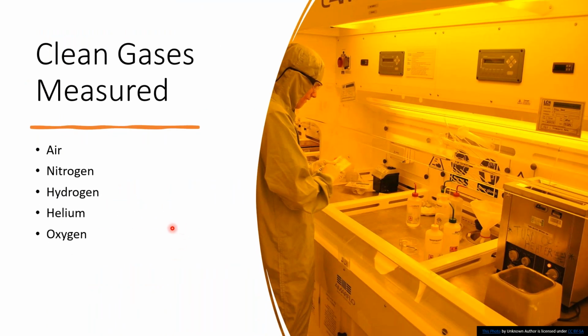Other gases that we measure on a regular basis, like I mentioned, we do a lot of airflow measurement. We do a lot of hydrogen, nitrogen, helium, oxygen, you name it. We're doing these on a regular basis. And some people say, well, you're measuring air, everybody can measure air. And it's like, yes, but we're measuring air in lots of different environments, whether it be food and beverage, where they're maybe using heated air and need a clean instrument to do that, or a pharmaceutical, or maybe you want to find out what department is using your compressed air. So these are all different applications and why thermal mass could be effective and could be used in these things.